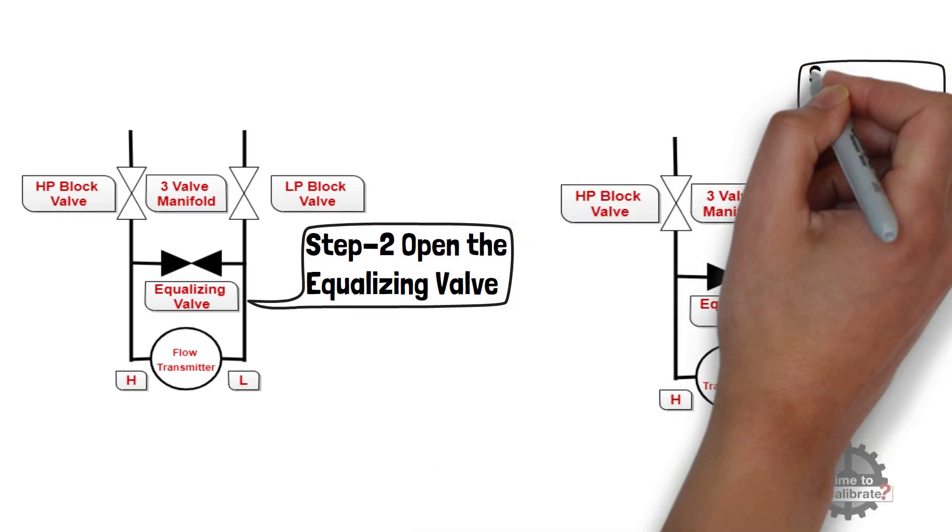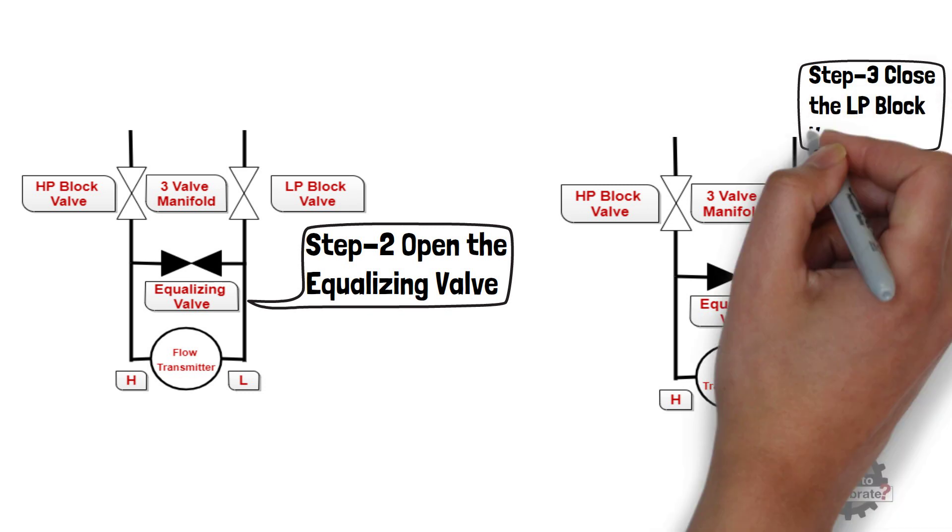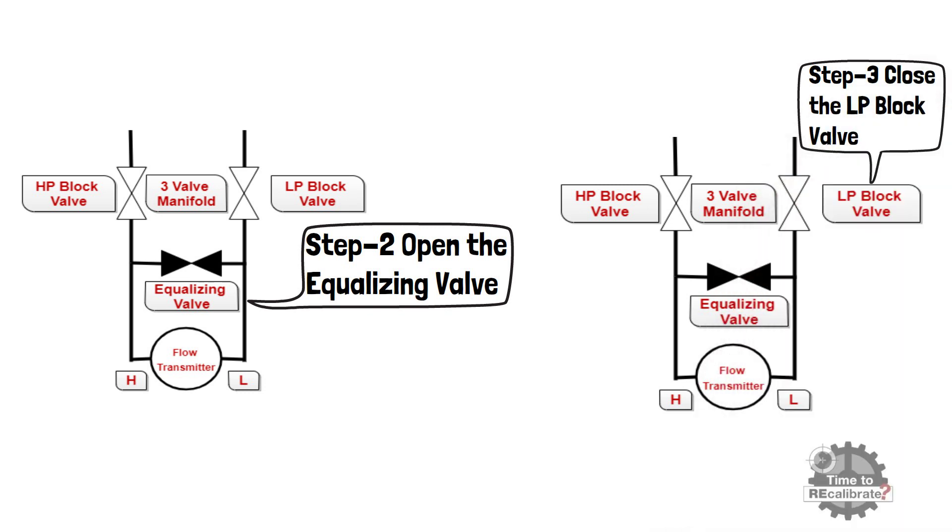In third step, close the LP block valve by rotating valve in clockwise direction. This will isolate the transmitter from the low side pressure.